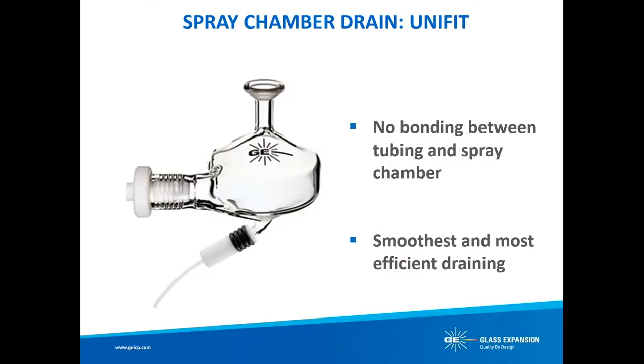Just a quick note on spray chamber draining. All GE spray chambers designed to be pumped come with a Unifit drain connector. As opposed to common PVC tubing that is often just slung directly over the spray chamber drain — which can eventually bond to the glass or quartz — the Unifit easily slides over the drain and provides a proper seal for smooth and efficient draining. The lack of a proper seal can lead to poor analytical results.